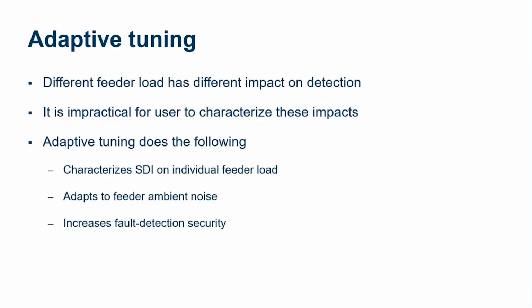Now, I mentioned tuning a little bit, and this is an important part of this AST protective element. When we go to set our traditional 50-51 elements, we have a pretty good idea of the maximum loading and the maximum and minimum fault current available. We have that information available from our power system models in order to set our traditional protection. However, in this case, much of that baseline and what is typical is really going to depend on the type of loading on that circuit. So in most cases, we don't have a good feeling of what is typical interharmonic energy on this particular circuit.